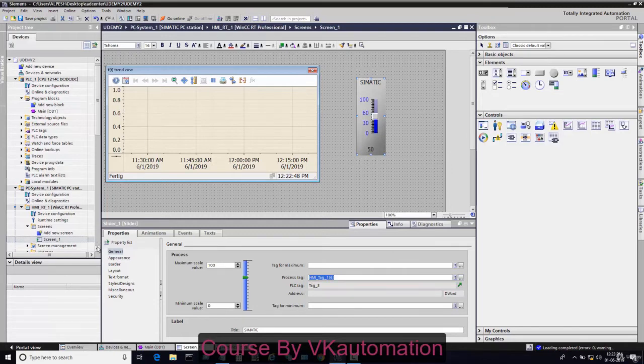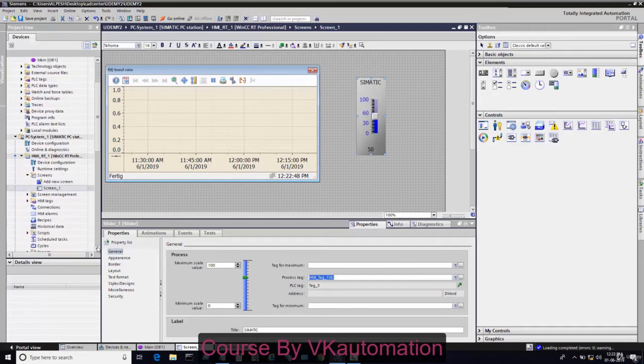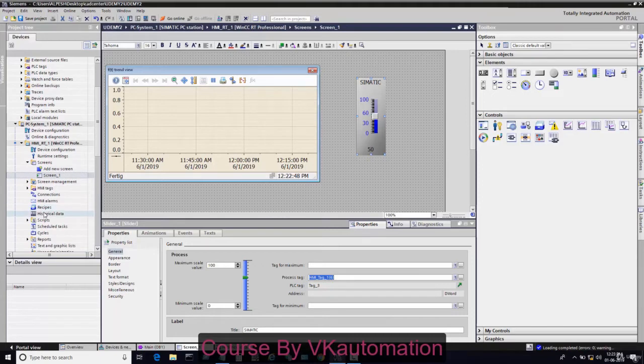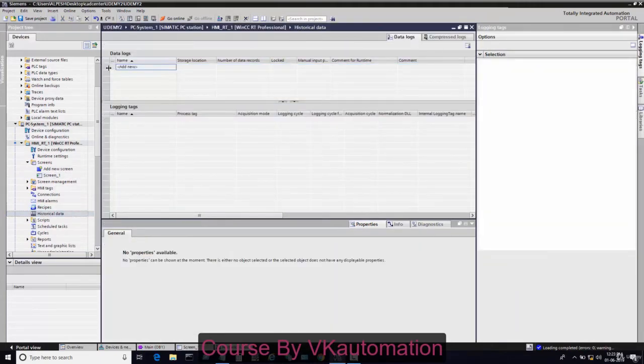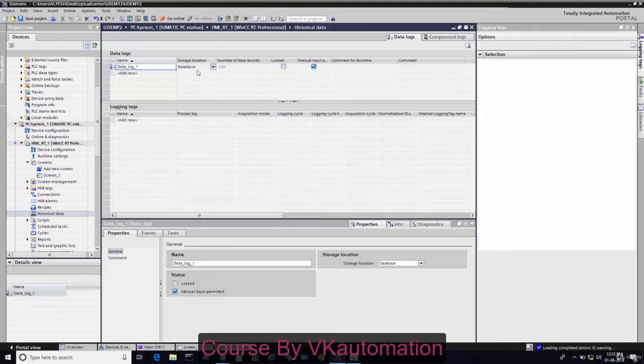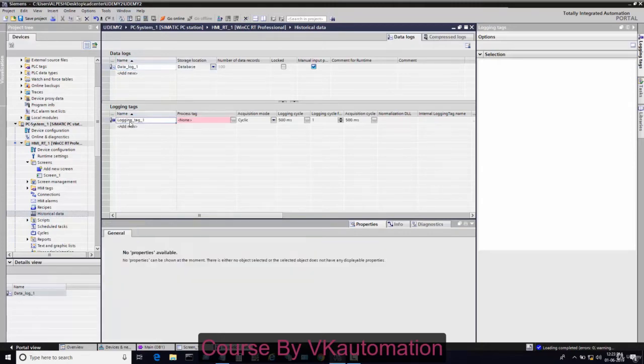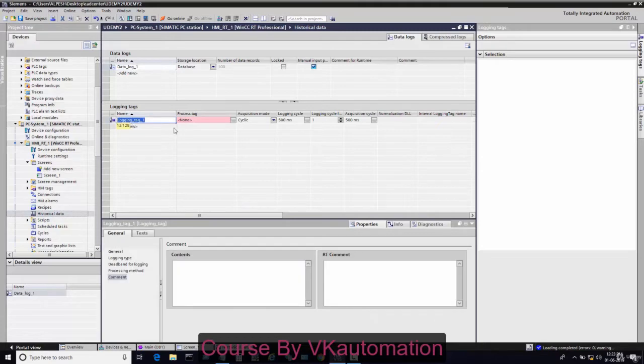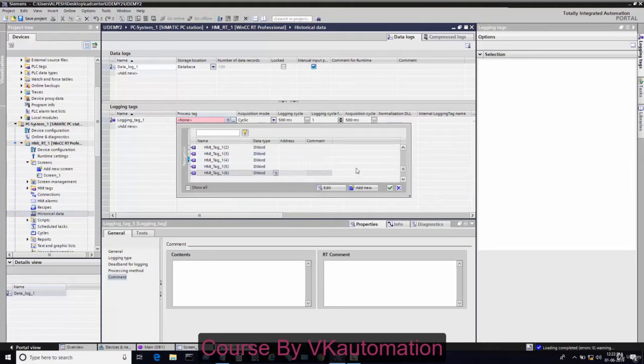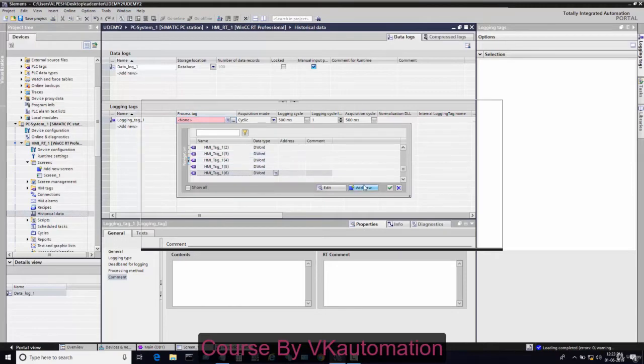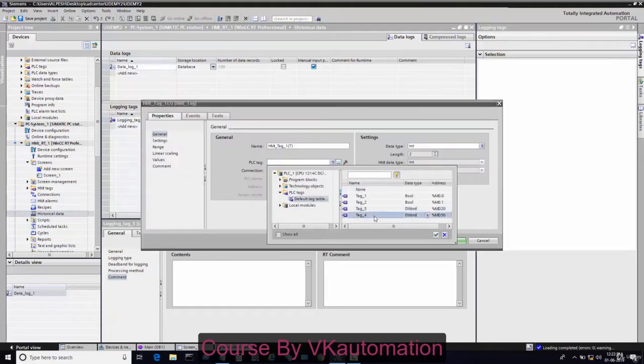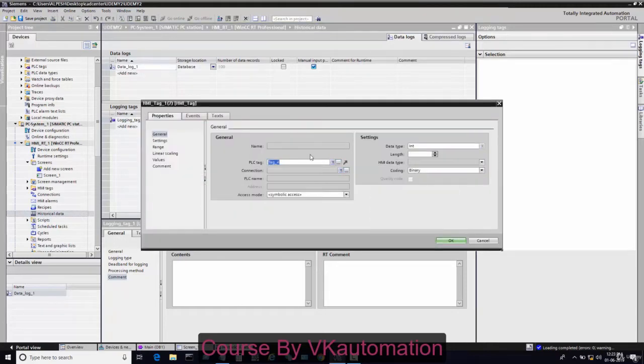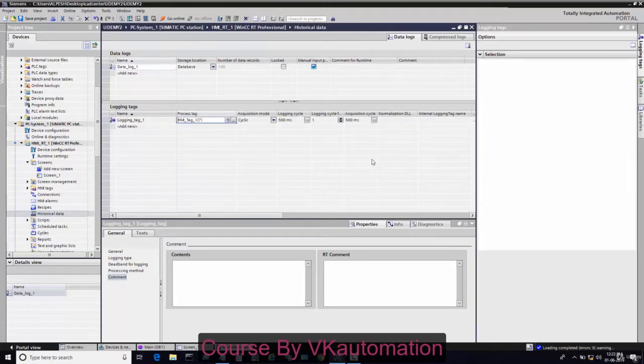Now I want to generate one data log. This data log will store the data in a database. This data log can have different logging tags. I will connect this logging tag as MD30, which we have generated in PLC. I will change the data type to real.